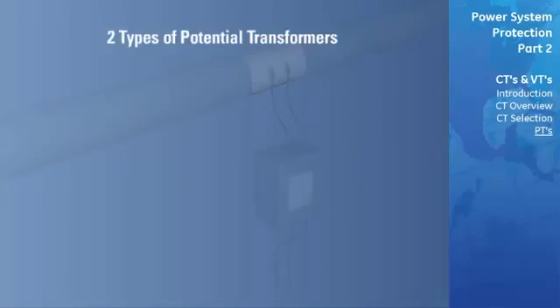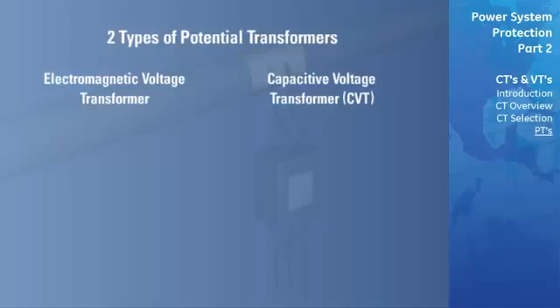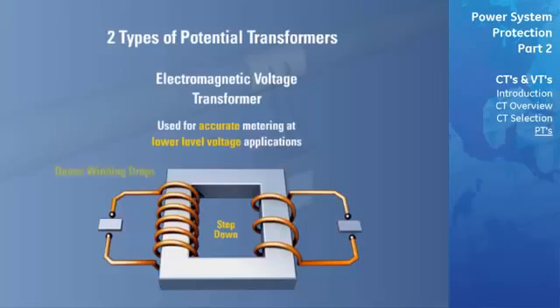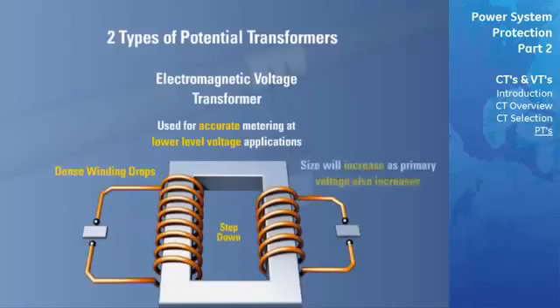There are two different types of potential transformers used today: the electromagnetic voltage transformer and the capacitive voltage transformer. Electromagnetic voltage transformers are usually used when accurate metering needs to be performed for lower voltage applications. Capacitive voltage transformers are commonly used in high voltage transmission line applications where the voltage is higher than 66 kilovolts. Electromagnetic voltage transformers have dense winding designs to accurately scale down the voltage and ensure the ratio is consistent for all variations in the input voltage. Due to the small amount of voltage drops per winding, the electromagnetic voltage transformers will increase in size as the rated primary voltage also increases. Likewise, the cost of electromagnetic voltage transformers tends to increase at a disproportionate rate to the primary voltage rating.